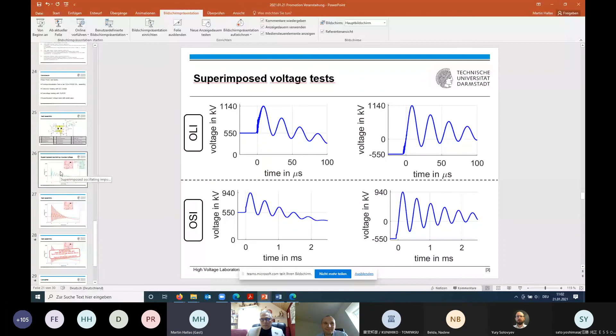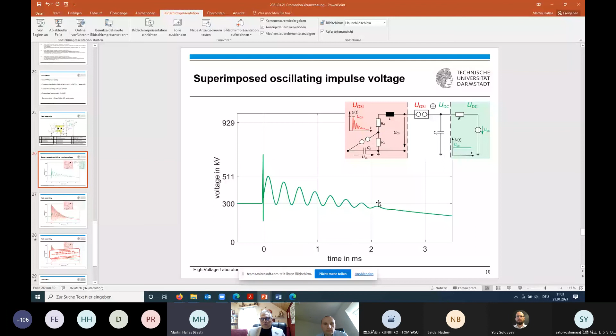So there is a certain effect which comes with that. It's here on this slide, I've copied them quickly into the presentation. This is the electrical circuit. You have the generator which generates the oscillating switching voltage, the generator generating the DC voltage, and the device under test, which is mainly a capacitance. When the spark gap connects it directly, you get the overall shape like that. You have an oscillating impulse voltage and the capacitance is quite high, so you get such a shape.